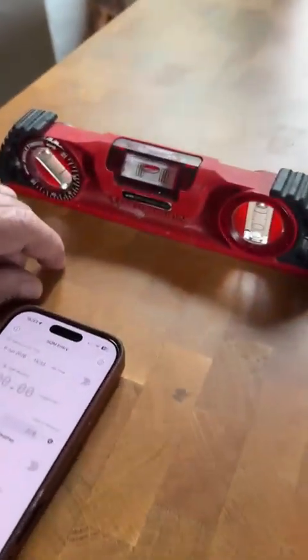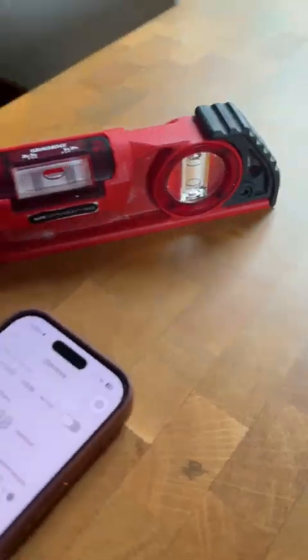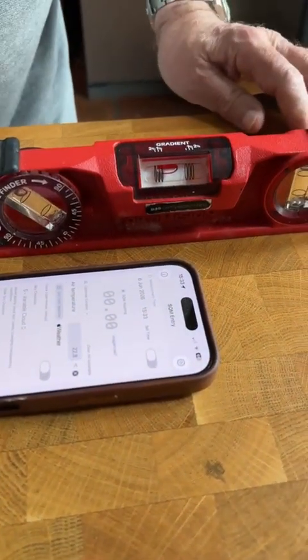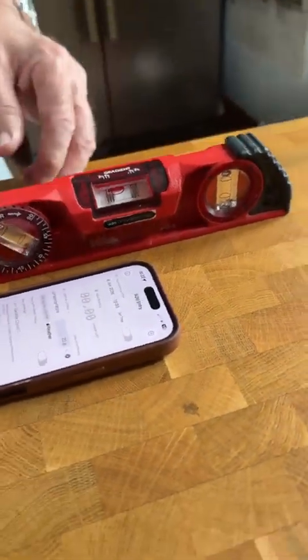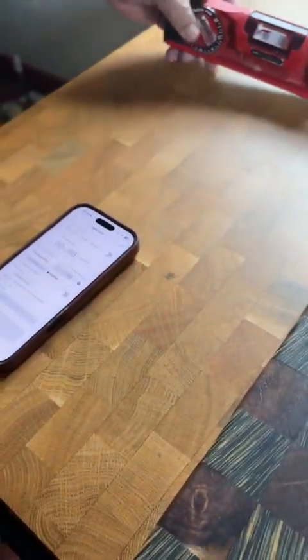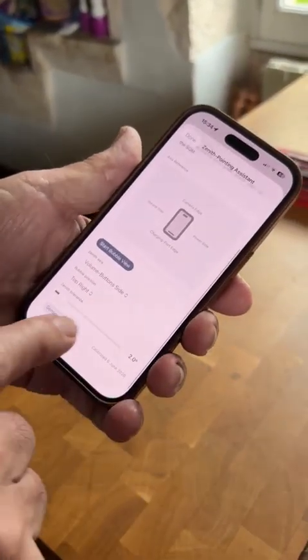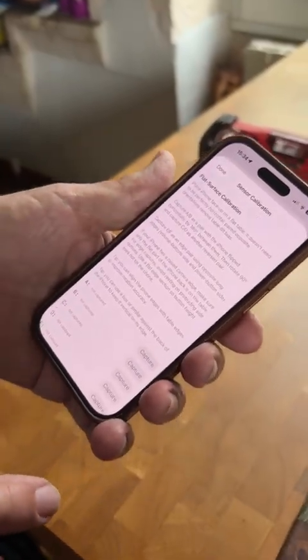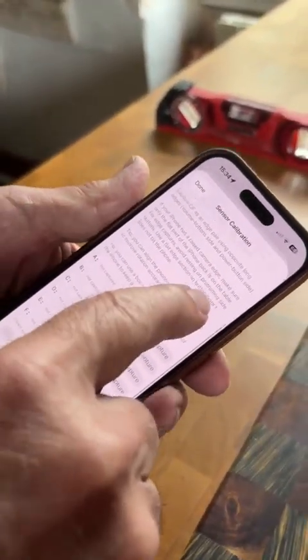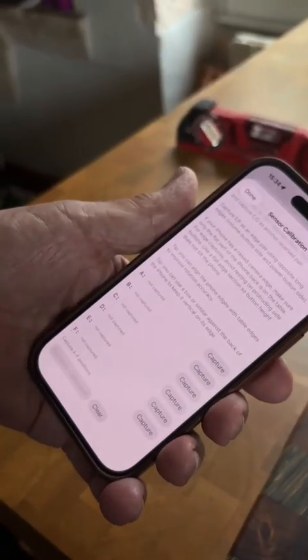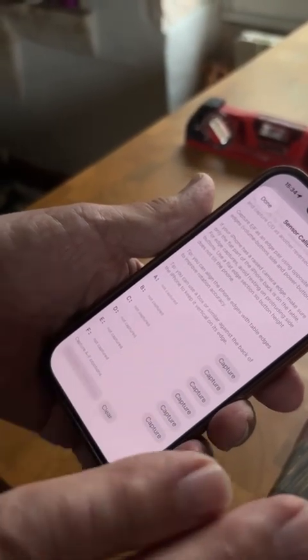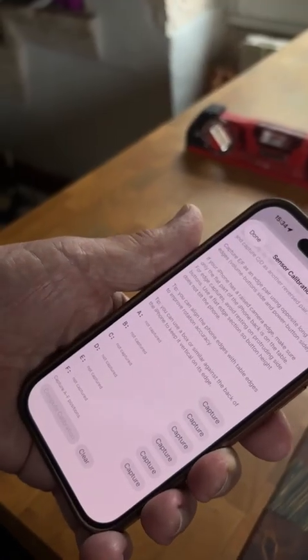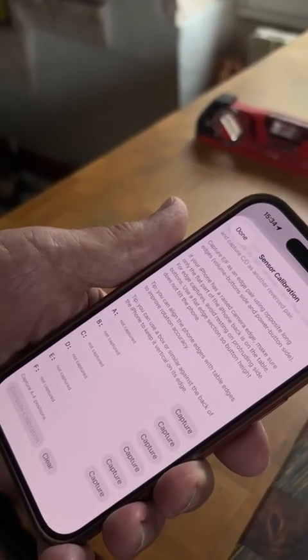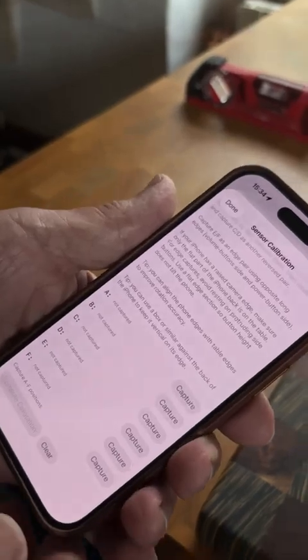We can see it's slightly off level in that direction, but as we move to this direction we can see that it's out by 2 degrees. That's not important because the calibration will take that out. To get to the calibration, we go to the zenith pointing assistant, sensor calibration, which calibrates the sensors in the iPhone itself, and we have to enter 6 values. That's 2 per axis for the 3 axes of the phone, and 1 in each direction for the axis so that we can compensate for slope in the table.